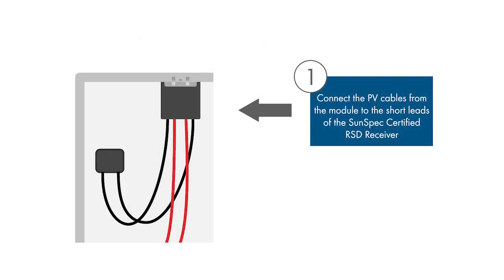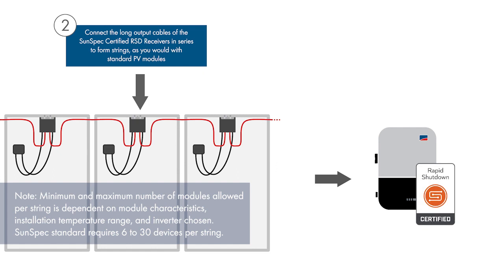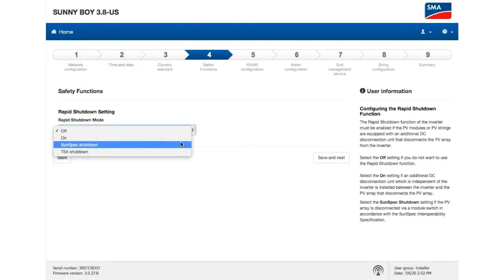Once all the modules have been connected to their shutdown receivers and the output leads connected as strings, the strings can be connected to an SMA inverter equipped with a built-in SunSpec certified shutdown transmitter. When the inverter's built-in SunSpec certified transmitter is turned on, the shutdown receivers will allow their modules to operate and the string voltages will change to the appropriate open circuit voltages based on the module type and number of modules in each string.